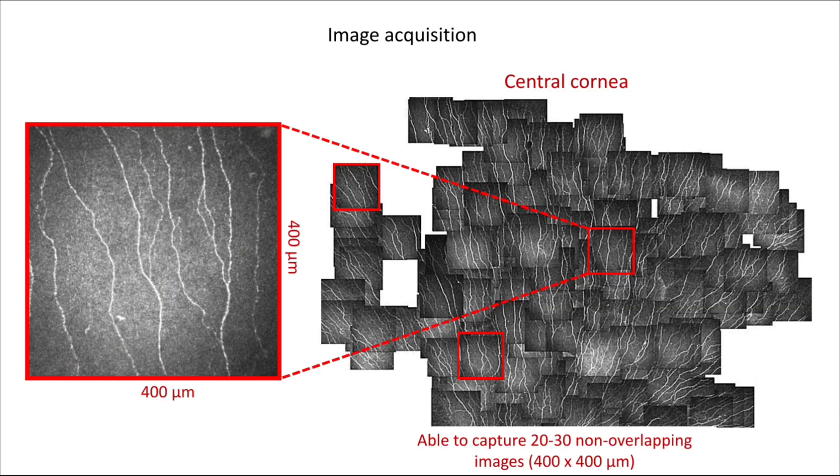A single image taken by the HRT device has dimensions of 400 micrometers by 400 micrometers, and you should be able to capture about 20 to 30 non-overlapping images within the central cornea.